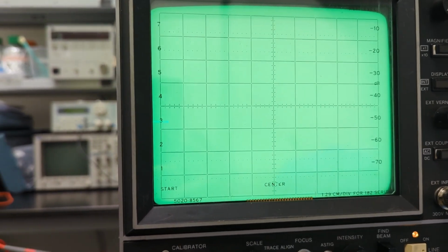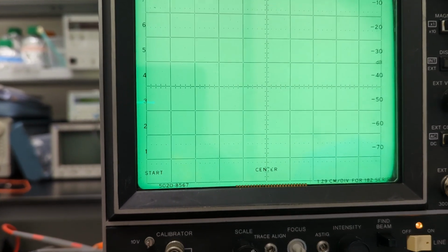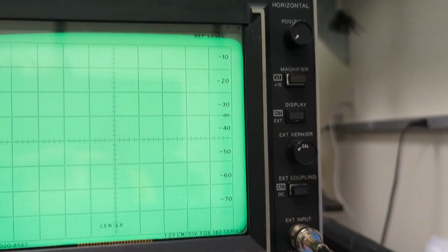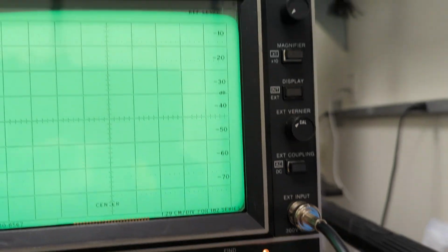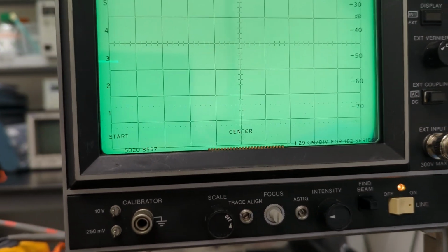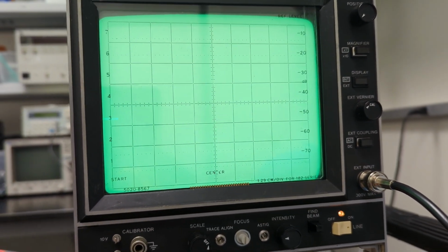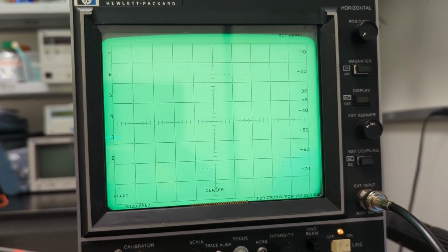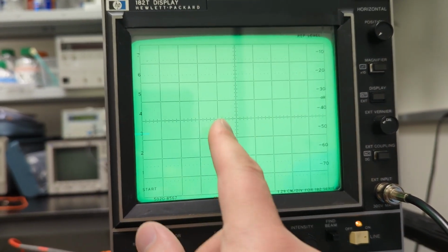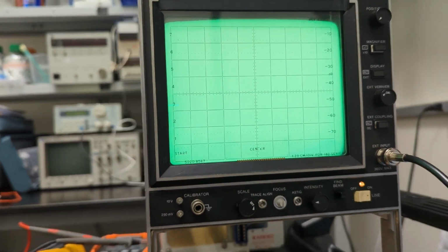And then you'd be able to check the unit, as long as you have the external input selected for the display and not internal, which would be using the plugin's horizontal amplifier. Now there were just 2 dots on the screen, and it started in the center, and then it moved over, and then it just went right off the screen.